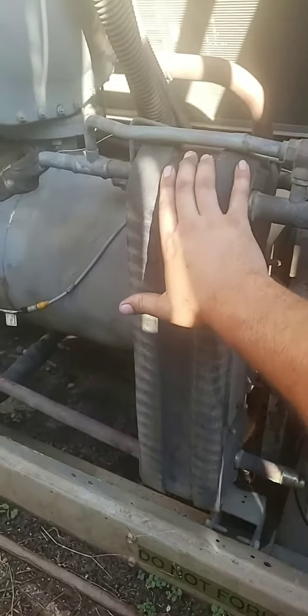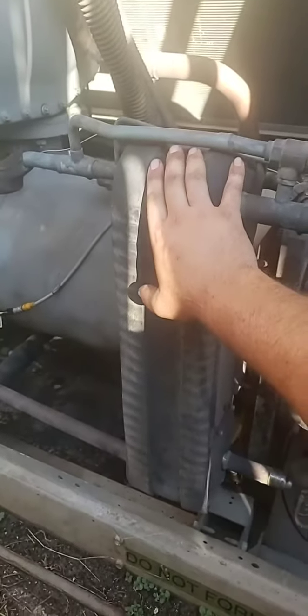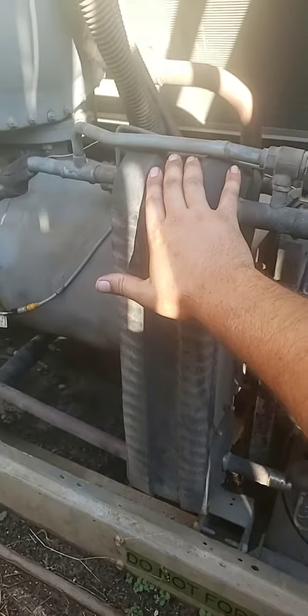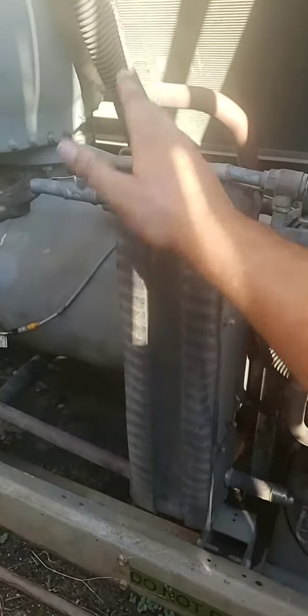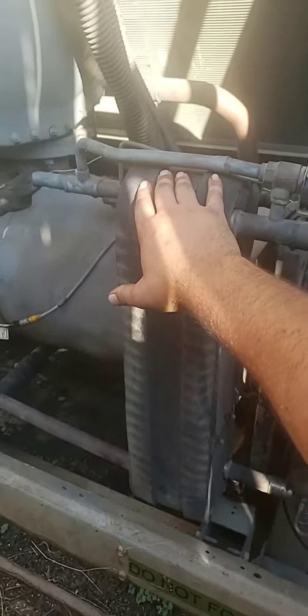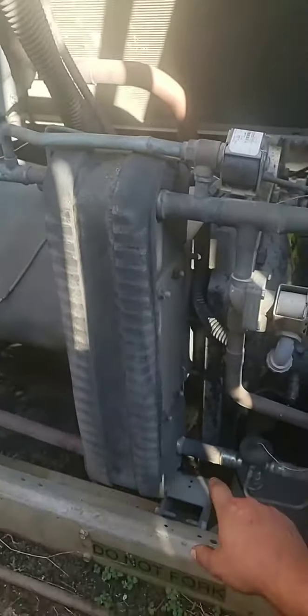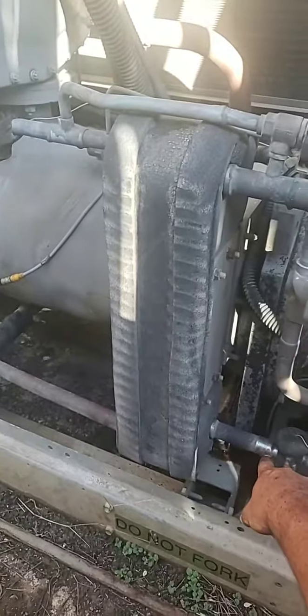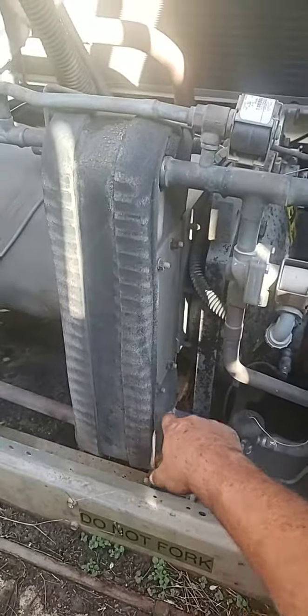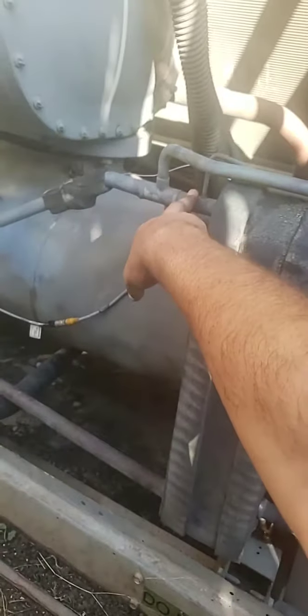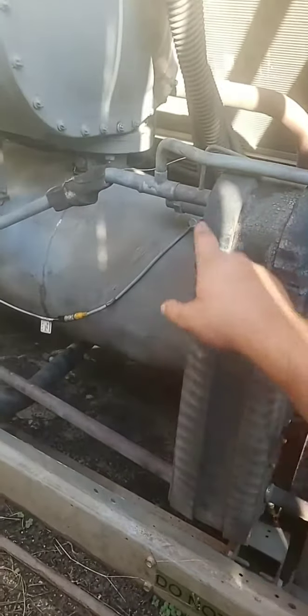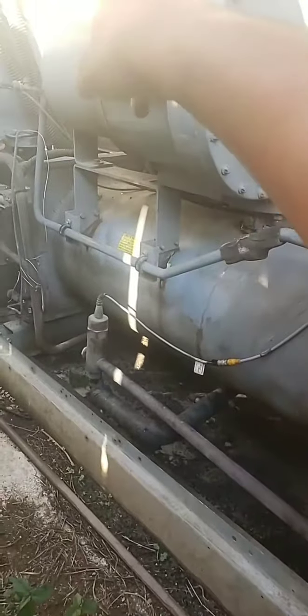This is very common to see, especially this type of setup on a lot of your chillers, even water to water, or water cooled chillers, I should say. They have a very similar setup to accomplish that. Like I said, after that TXV, when it goes in and where the liquid goes in, those 2 circuits don't mix with each other. Okay, they stay independent. But this line here, as it comes back out, it does go all the way back into the motor.